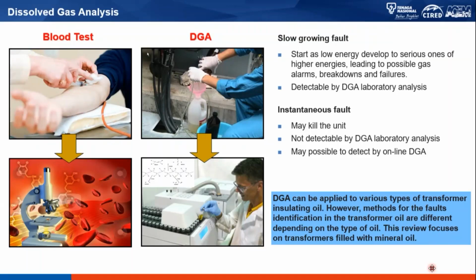Sometimes faults occur out of nowhere, what we call an instantaneous fault, with no sign from historical DGA whatsoever. If we're still depending on DGA laboratory analysis by taking samples every 12 or 6 months, that won't help. What will help is having an online sensor embedded in our transformer that has a higher chance of giving warning before the instantaneous fault happens.